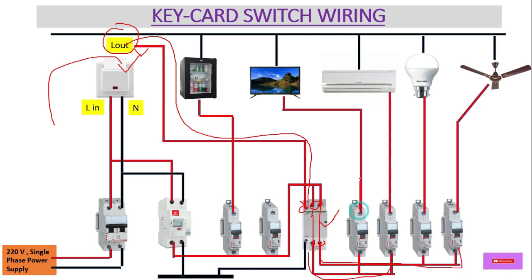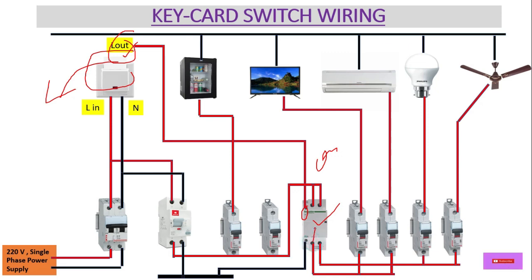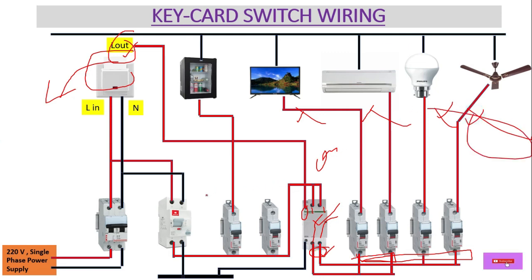With the contactor energized, power is fed to individual appliances like the fan, lights, AC, and television. When we again remove the card, power is lost at L-OUT, the contactor coil loses supply at A1, the contactor de-energizes, the circuit breaks, and it becomes NO again — no power at the output, so all MCBs lose power and all loads are turned off automatically. This is how the key card switch system works.